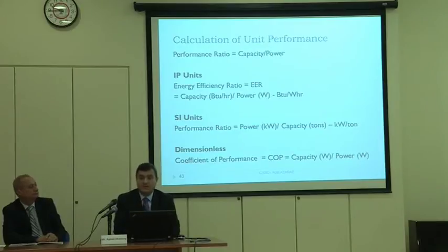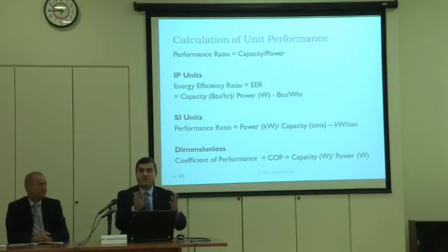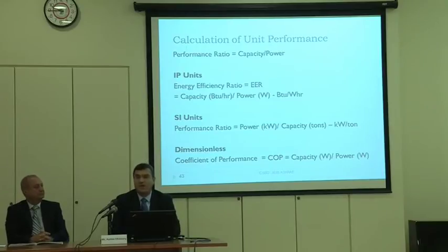It's the other way around: it is kilowatt per ton, so the cooling is in tons and the power of the compressor is measured in kilowatts. So when you hear EER or kilowatt per ton, they are almost the same, with opposite trends, but you can go from one to the other by simple conversion. And of course COP, as we all know, has no units, where we speak about cooling per power, both in the same units. So COP has no dimension.